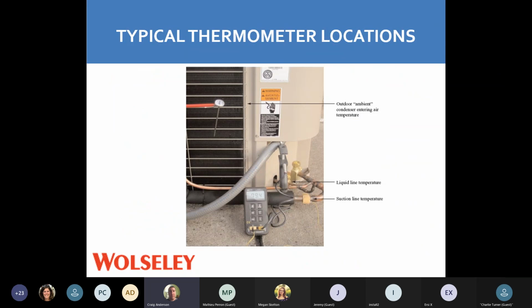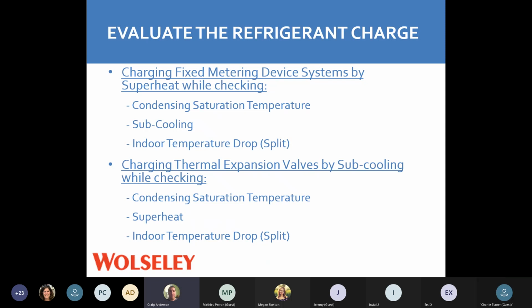Typical thermometer locations when we're doing our startup. We're going to check the airflow, the temperature that's going into the coil. Just make sure you're not in the sunlight so it's getting a proper reading. Clamp-on meters are perfect. We want to clamp onto our liquid line and our suction line when we're doing our testing. So charging a fixed metering device system by superheat. So that's your piston. Superheat while you're checking your saturation temperature, which we'll go through, your subcooling and your indoor temperature drop, so that you're split between your return and the supply. Charging with a TX valve by subcooling while you're checking your saturation temperature, your superheat as well, and your indoor split. So we're wanting to check all this stuff once you get that unit running.